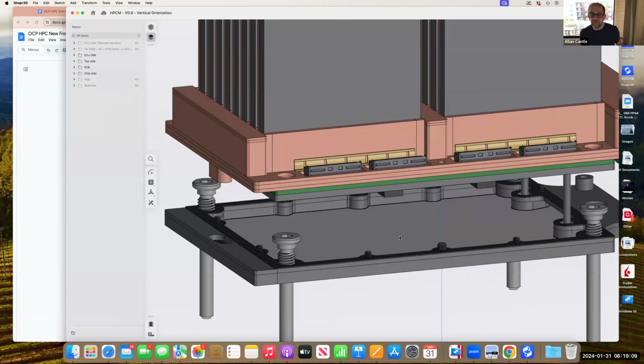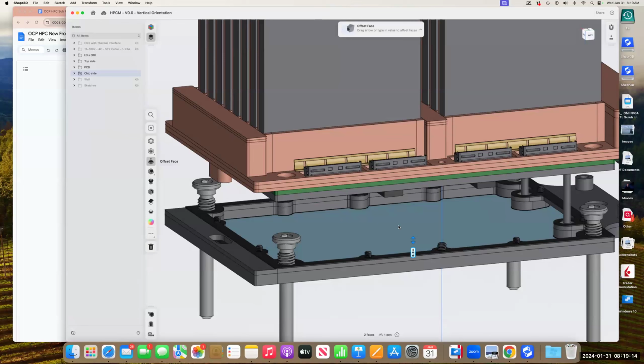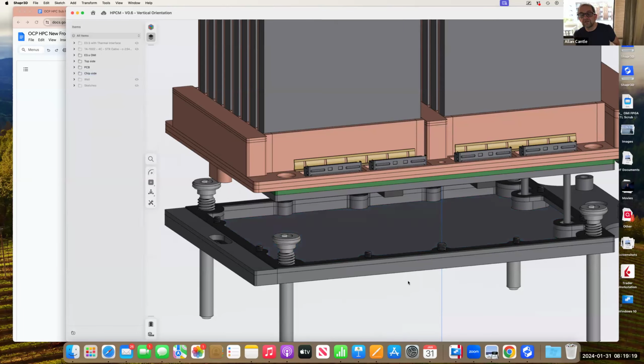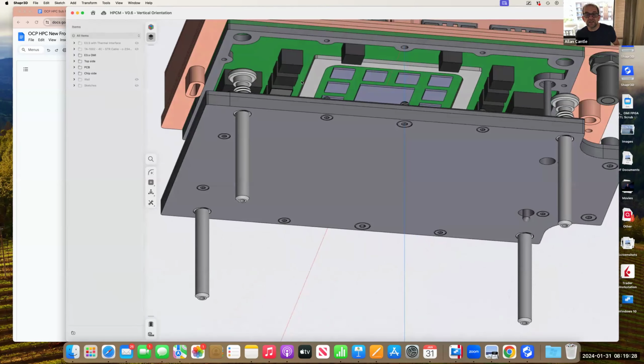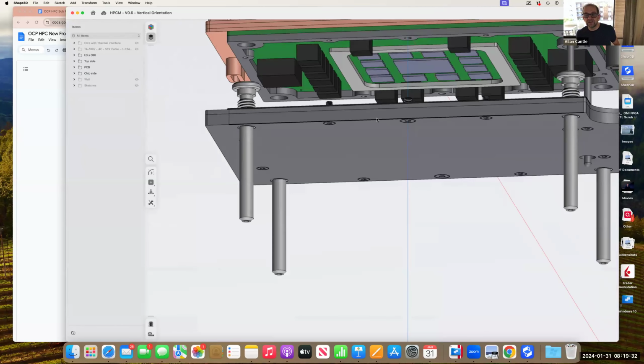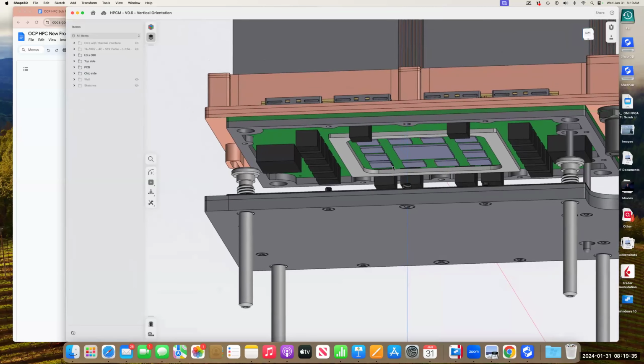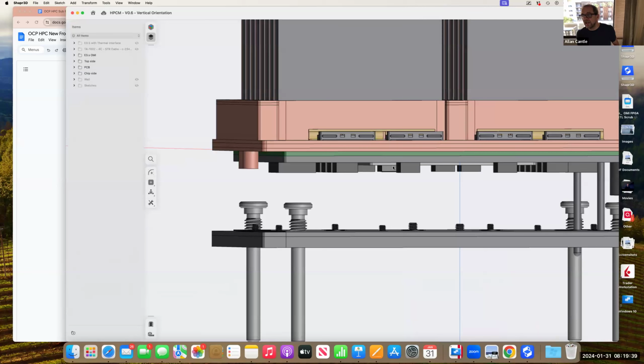So the center is going to bear the biggest force, it's going to be sucked in, or pushed out, depending on which cooling system. That's what the gentleman from Boyd was talking about last week. No, completely agree. He was saying you need more screws here, closer to the chip, because he had this two-phase mechanism with a separate loop for the chip. So that would mean more holes. He's trying to stop that cover from bending. But the pressure is 8 psi, you said, compared to his 40 psi, right?